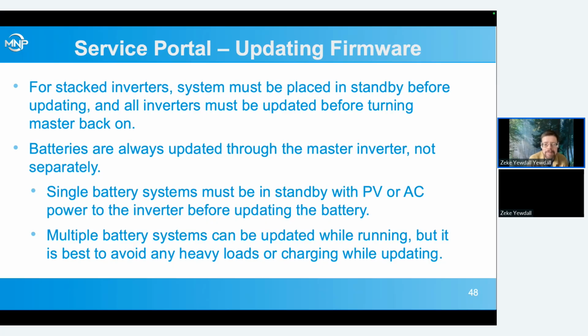If you have a battery system with just one battery, it needs to be in standby with either PV power or AC power to the inverter before updating the battery, because the battery will turn on and off during the process. If you have a system with multiple batteries, you can update that while it's running because it'll only turn them on and off one at a time, but it's best to avoid any heavy loads while you're doing that.